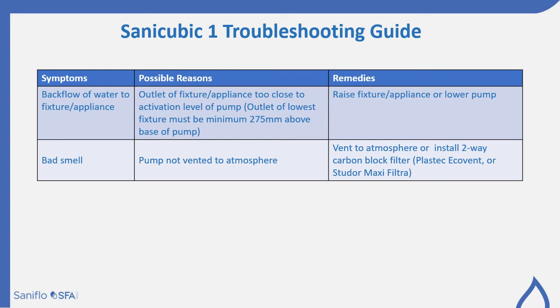If you have a backflow of water running back up through to the fixture or the appliance, it's possible that the fixture or the appliance is too close to the activation level of the pump. As a guide, we recommend that the base of the pump must be a minimum of 275 millimeters below the lowest fixture. In this instance, you would raise your fixture or you would lower the pump.